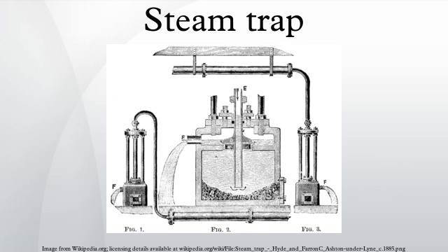Basic operation: the simplest form of steam trap is a disc or short solid pipe nipple with a small hole drilled through it, installed at the lowest point of the equipment. Since steam condensate will collect at the lowest point and live steam is about 1200 times greater in volume than this hot liquid, condensate is effectively removed and steam is blocked.